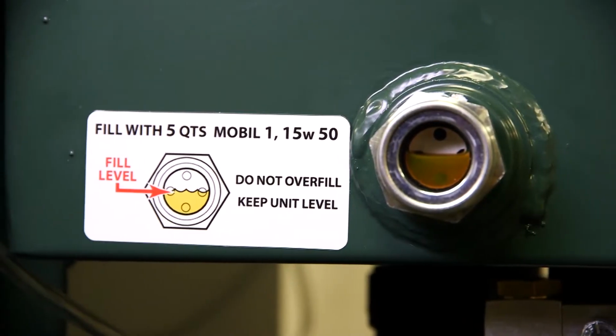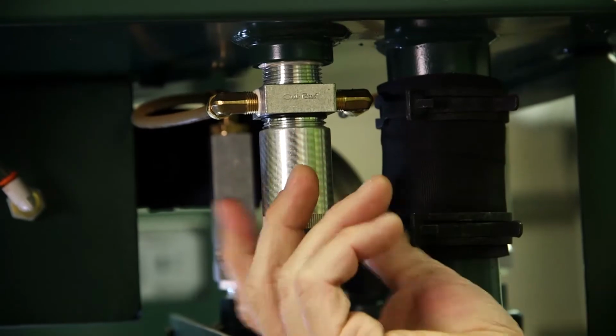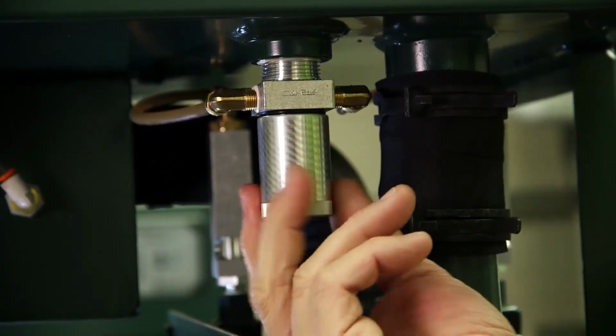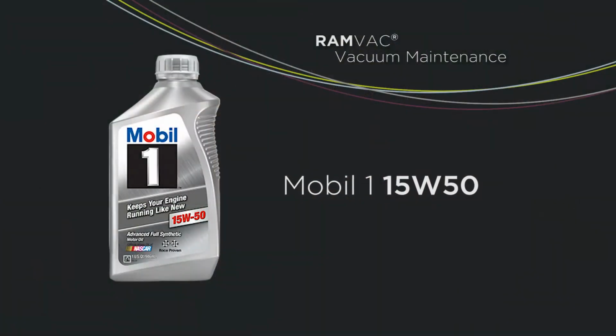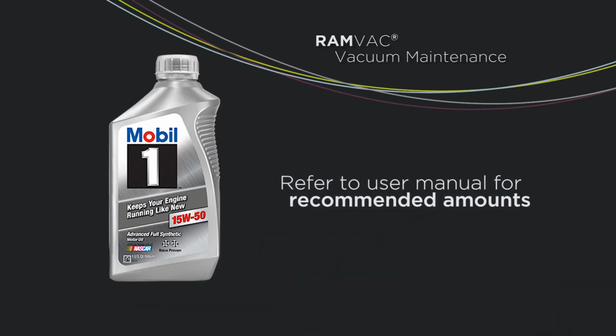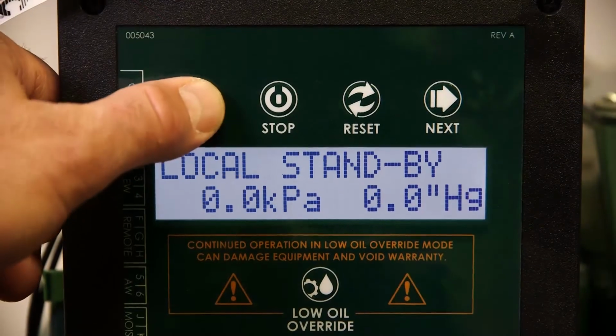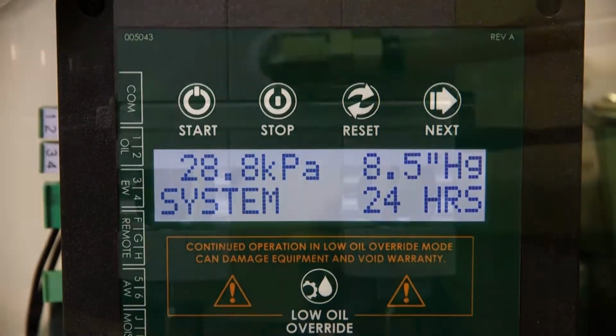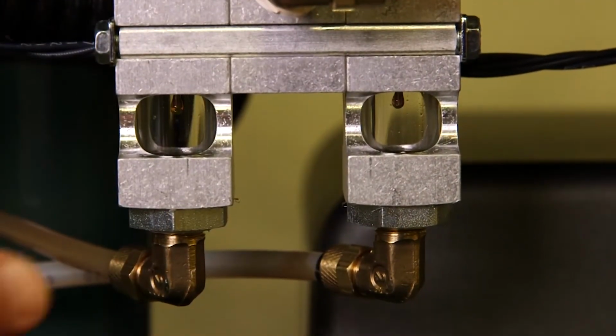Add clean oil into the canister. Then, install the oil filter canister. Mobil 1 15W50 is the specified brand and viscosity. Recommended amounts are included in the user manual. Start the vacuum and run for 10 minutes. Last, check the drip rate.